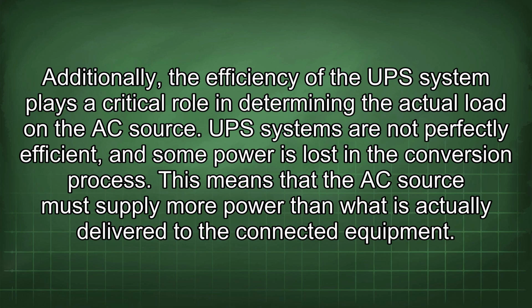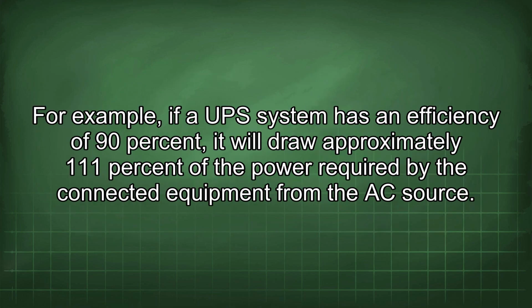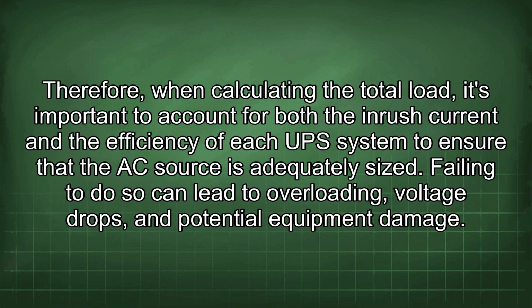Additionally, the efficiency of the UPS system plays a critical role in determining the actual load on the AC source. UPS systems are not perfectly efficient, and some power is lost in the conversion process. This means that the AC source must supply more power than what is actually delivered to the connected equipment. For example, if a UPS system has an efficiency of 90%, it will draw approximately 111% of the power required by the connected equipment from the AC source. Therefore, when calculating the total load, it's important to account for both the inrush current and the efficiency of each UPS system to ensure that the AC source is adequately sized. Failing to do so can lead to overloading, voltage drops, and potential equipment damage.